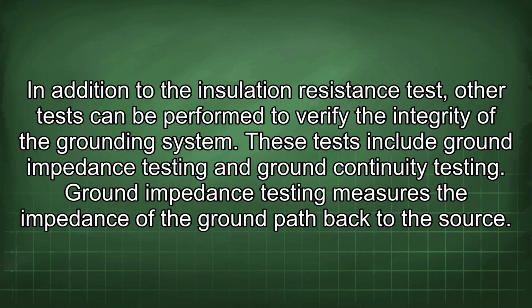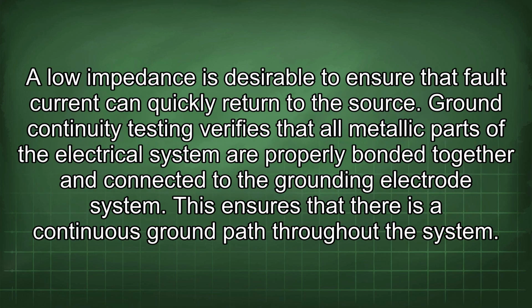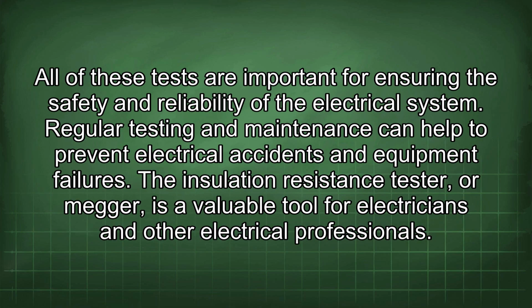In addition to the insulation resistance test, other tests can be performed to verify the integrity of the grounding system. These tests include ground impedance testing and ground continuity testing. Ground impedance testing measures the impedance of the ground path back to the source. A low impedance is desirable to ensure that fault current can quickly return to the source. Ground continuity testing verifies that all metallic parts of the electrical system are properly bonded together and connected to the grounding electrode system. This ensures that there is a continuous ground path throughout the system. All of these tests are important for ensuring the safety and reliability of the electrical system. Regular testing and maintenance can help to prevent electrical accidents and equipment failures.